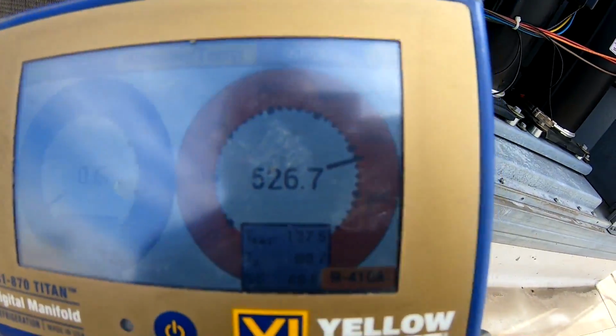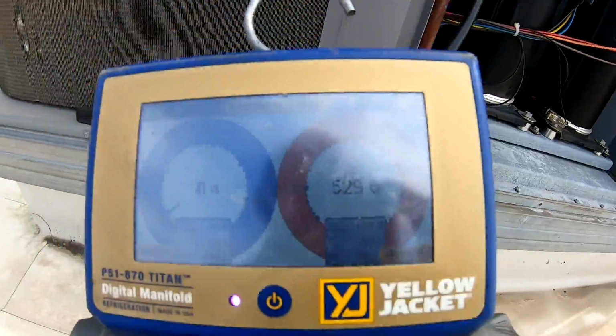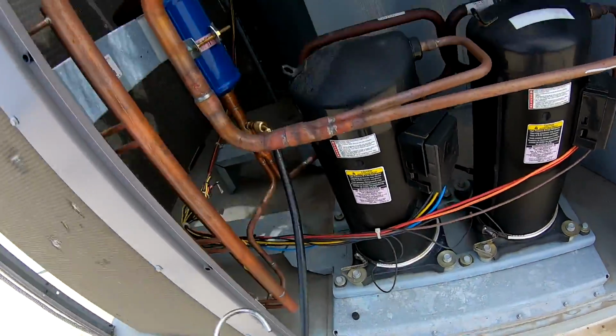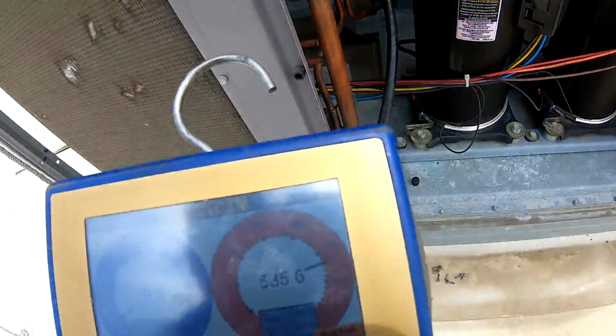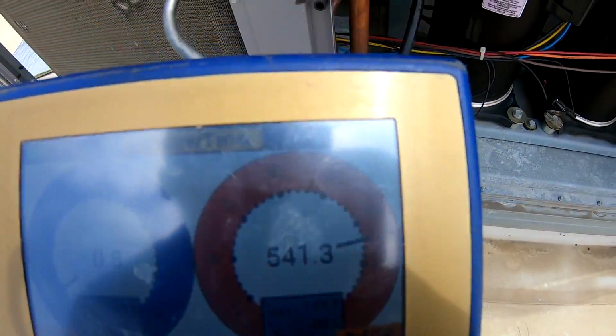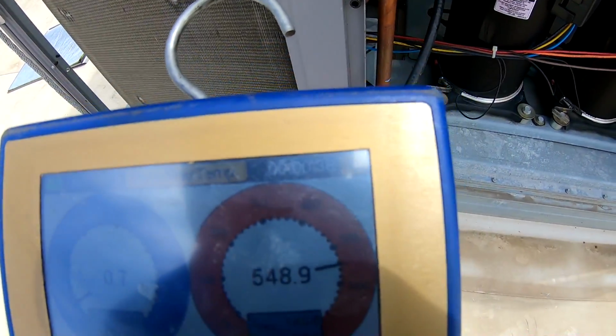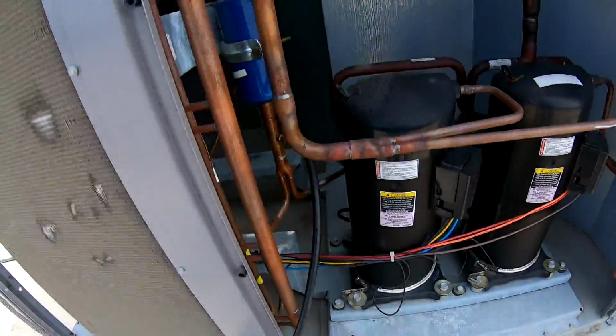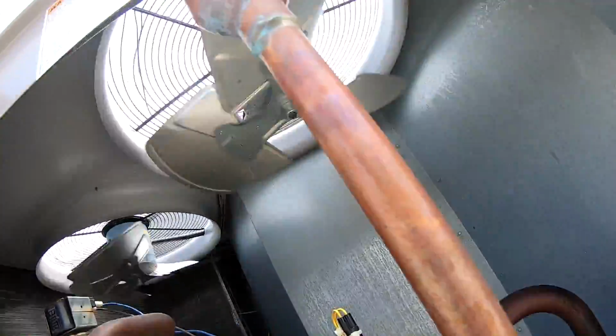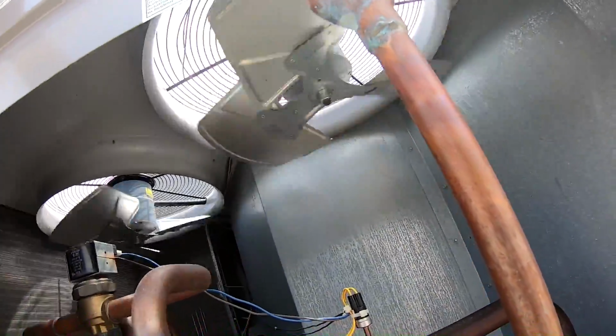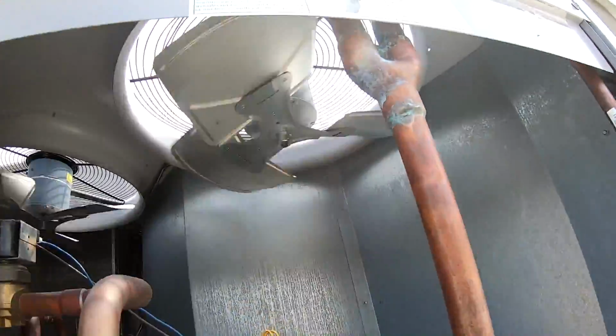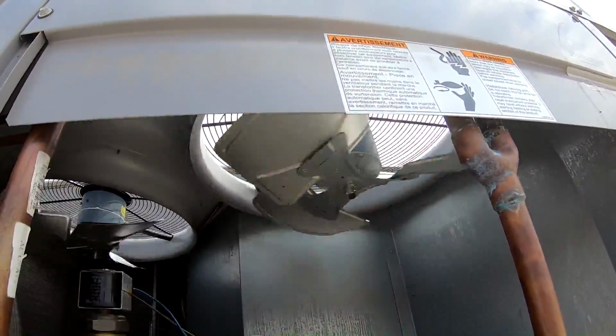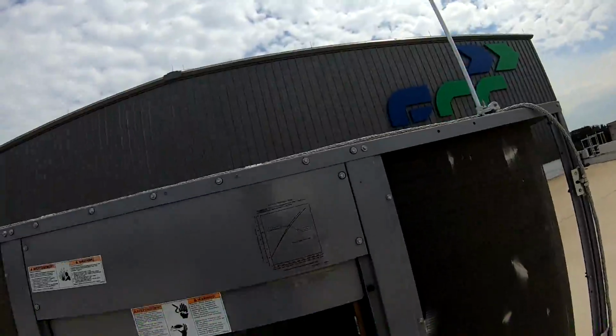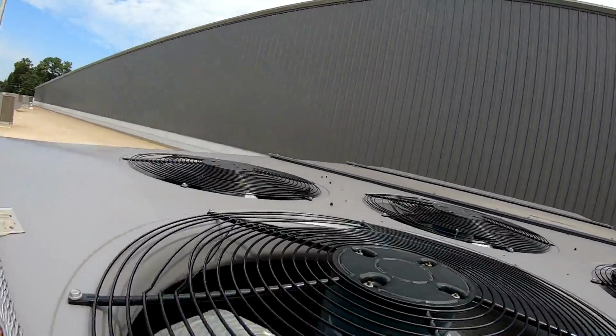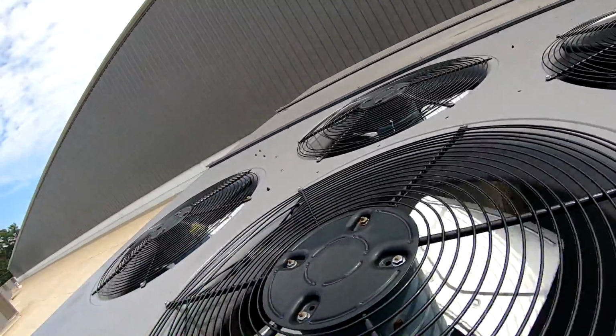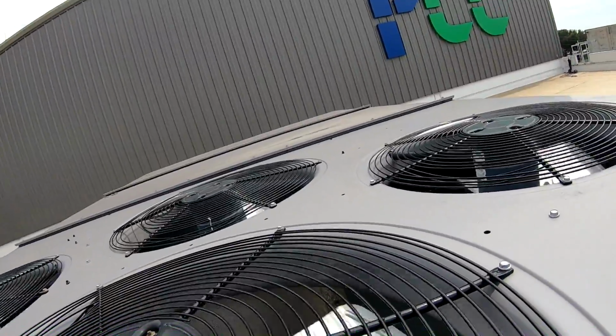You see it's going up. 127 for the liquid line anyway, going to the filter dryer. So you know it's going off on high head pressure. So we got to find out why those fans are not running. So I'm gonna track down and look. Looks like none of them are running. So it seems like it should be a common problem.